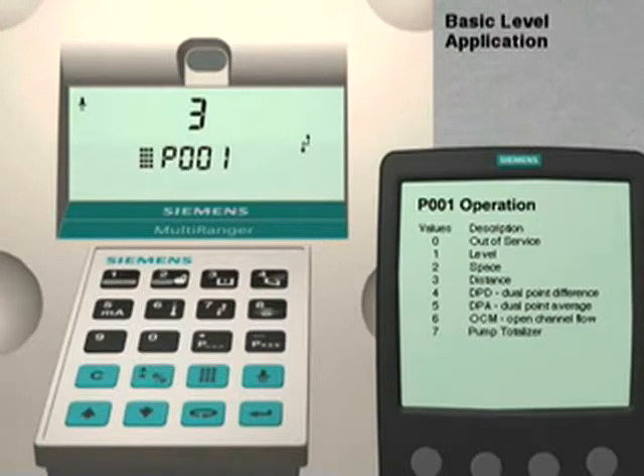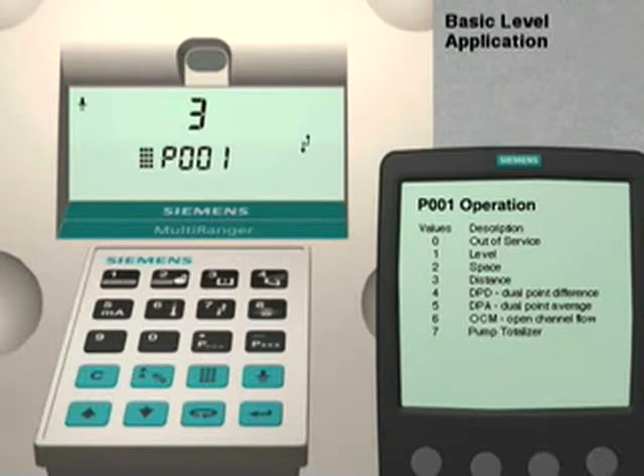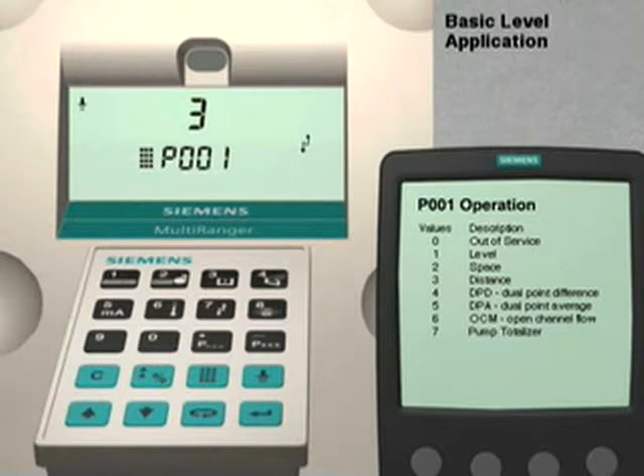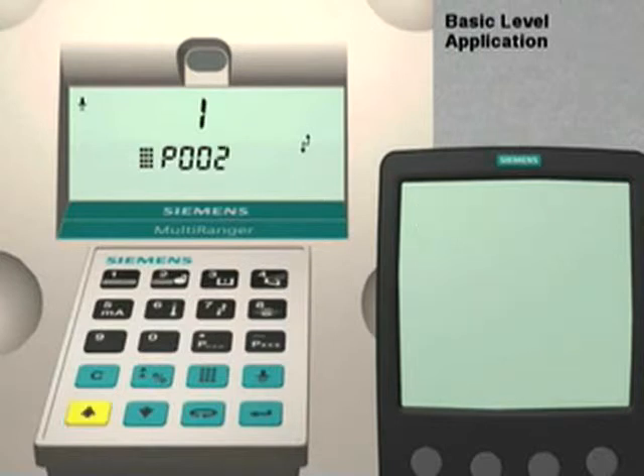Parameter 1 sets the type of measurement for the application. As you can see, it is currently set at 3, which is the factory default value. With this value, the multi-ranger would measure the distance from the transducer to the liquid surface. For our application, we want to measure the level — in other words, the height of the liquid in the vessel. According to the manual, parameter 1 for a level measurement should be set to a value of 1. Simply push the number 1 key followed by the Enter key. To go to the next parameter, press the up arrow key.